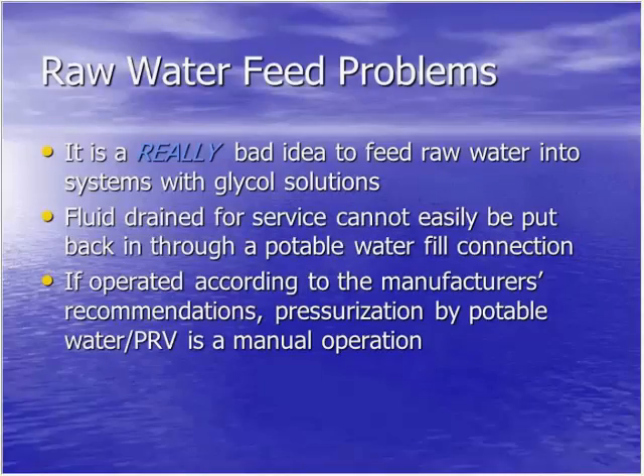And another problem is that it's really a bad idea to feed raw water into systems with glycol solutions. Obviously, glycol is in there for a reason. It's in there to protect the system from freezing. So if you fill it with more water, you're just going to dilute that freeze protection. Another reason: glycol manufacturers have minimum dilution requirements. Some say they don't want to see a concentration of glycol below 30%.